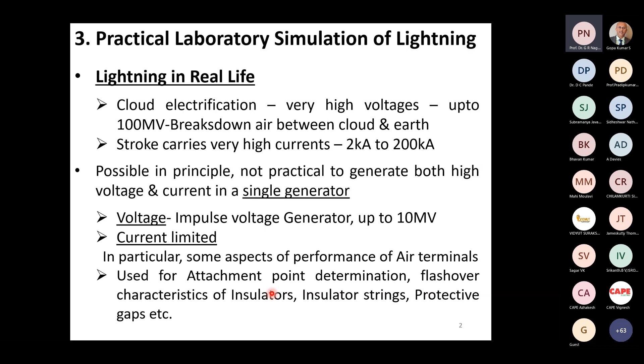Now, for current, you have separate current generators. I must emphasize again, as I have done many times earlier, voltage causes breakdown of the insulating path and allows the current to flow, and it is always the current which does the damage. The damage done by voltage is that it creates a path for current to flow, and the current does the damage for us, whether it's a fire hazard, building damage, human fatality, or whatever it is, all done by the current. Current capability can relatively easily go up to about 200 kiloamperes or even 300 kiloamperes.